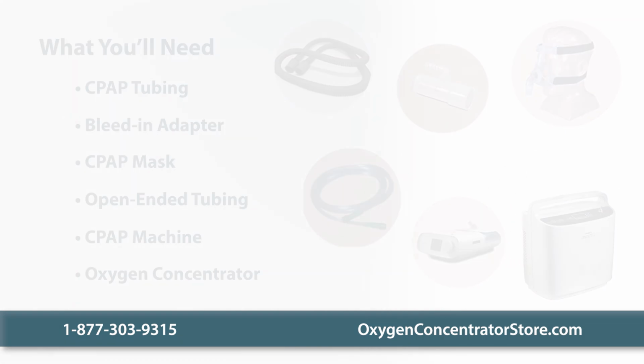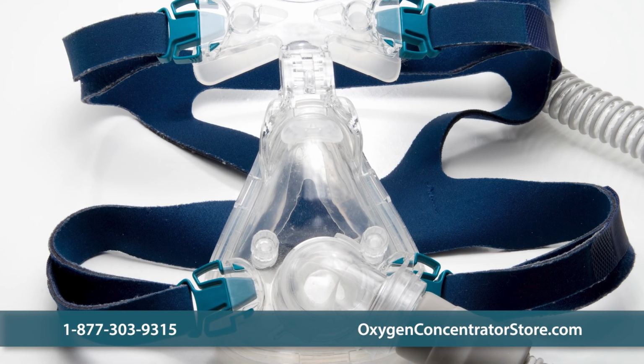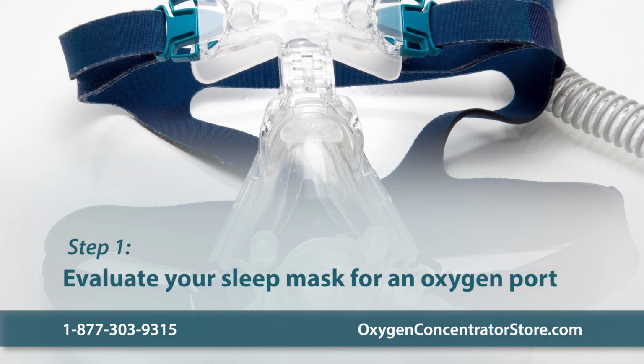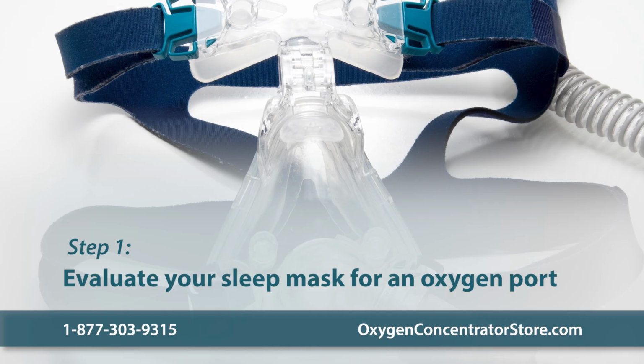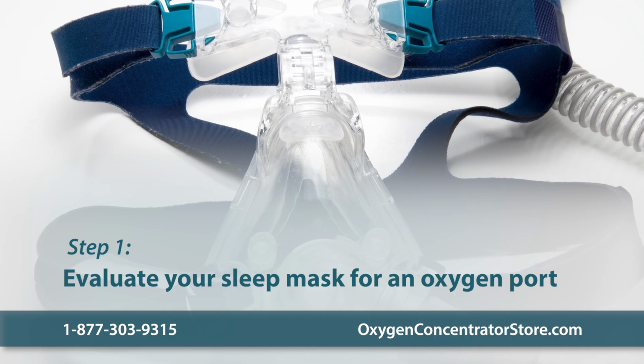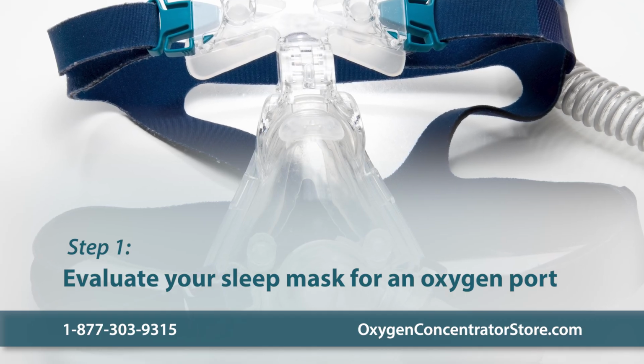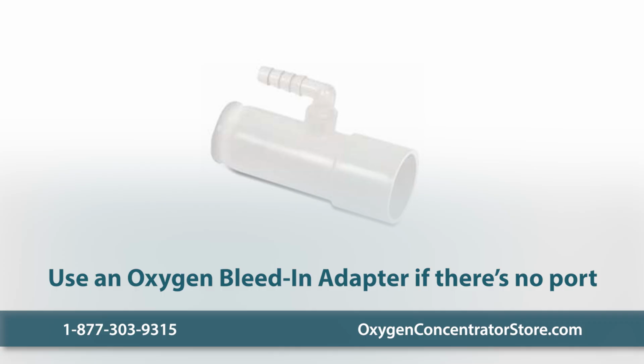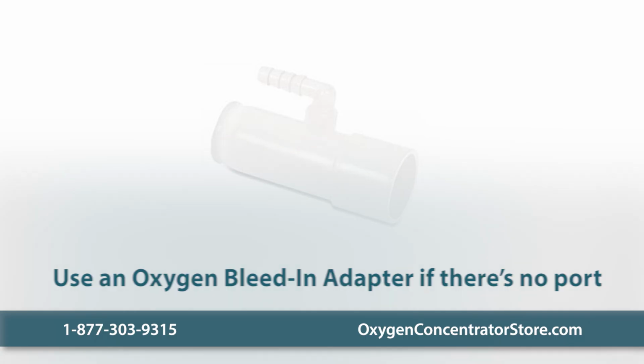In order to properly connect your CPAP device to an oxygen concentrator, you'll first need to evaluate the type of CPAP mask you have. Some masks feature an oxygen port. However, most masks do not and will require a small and inexpensive device called an oxygen bleed-in adapter. If your mask has an oxygen port, it may be covered with a small cap that you will be able to remove. Remove the cap by gently twisting and pulling until it pops off.